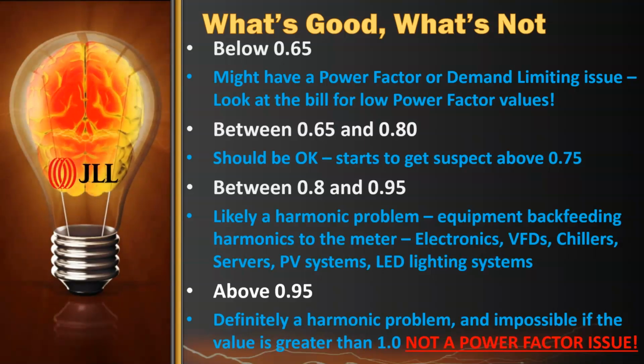There's so much of it right now, and there have been some changes in wiring practices, so that radiated harmonic energy will very often find its way back down the main feeder, go right to the meter, and the meter is just a counting device. It doesn't care which way the power is going; it just counts it. And so it counts that energy as energy that's going through the meter. That's the right way to put that.